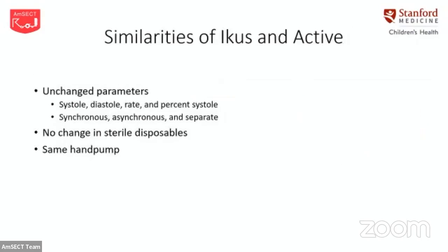So just to recap, with the Ikus and the active driver, there are no changes in the pump parameters that we're used to seeing. Those are all completely the same. All of the disposables are the same, and the hand pump is the same.